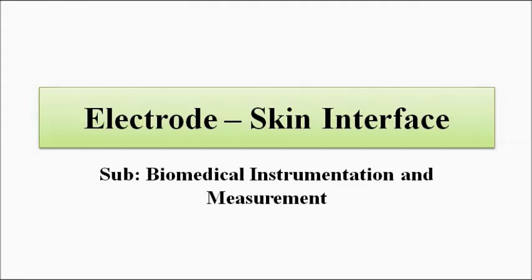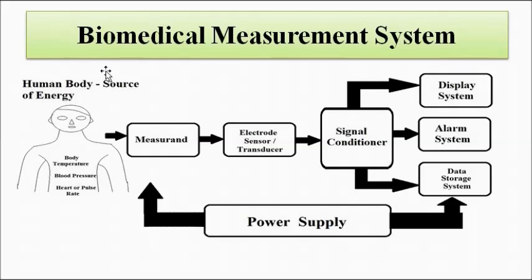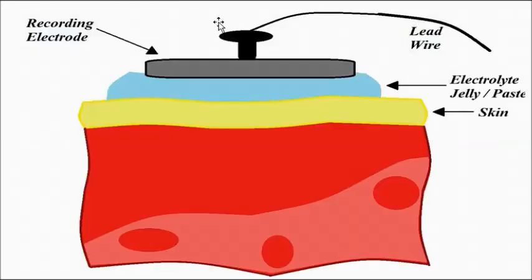In a biomedical measurement system, for the measurement of any physiological parameter — be it body temperature, blood pressure, heart rate, pulse rate, electrocardiogram, electromyogram, or electroencephalogram — we have to use an electrode. The sensor or transducer is associated with the electrode; it is connected to the specific body part, either placed on the surface or inserted into the body. So it comes in contact with the skin, and that gives rise to the electrode skin interface.